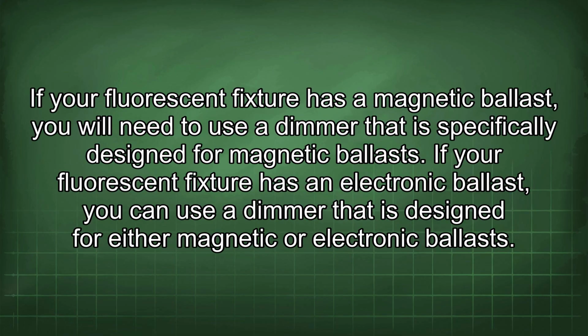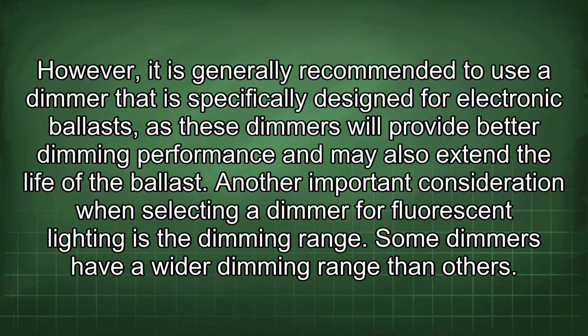If your fluorescent fixture has a magnetic ballast, you will need to use a dimmer that is specifically designed for magnetic ballasts. If your fluorescent fixture has an electronic ballast, you can use a dimmer that is designed for either magnetic or electronic ballasts. However, it is generally recommended to use a dimmer that is specifically designed for electronic ballasts, as these dimmers will provide better dimming performance and may also extend the life of the ballast.